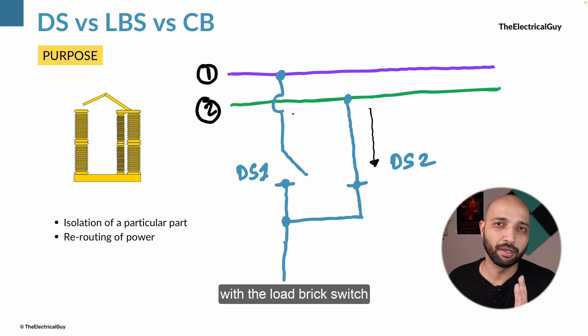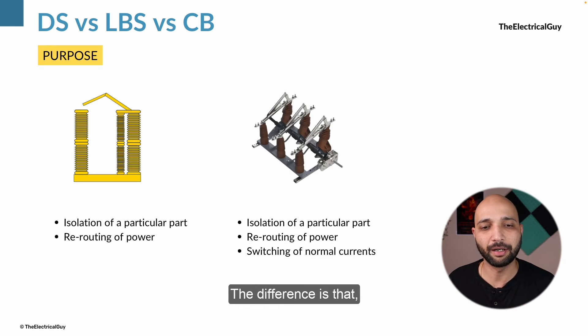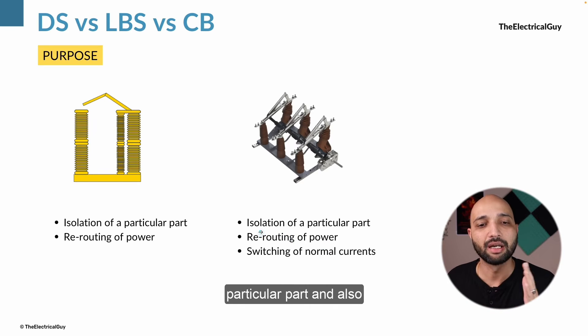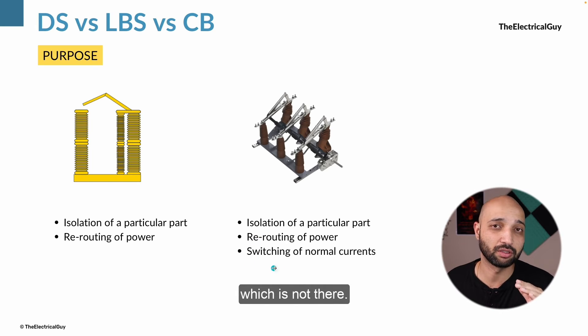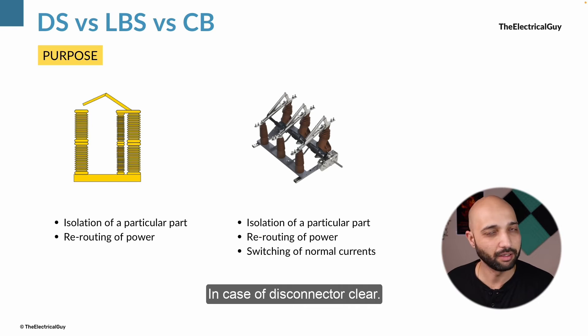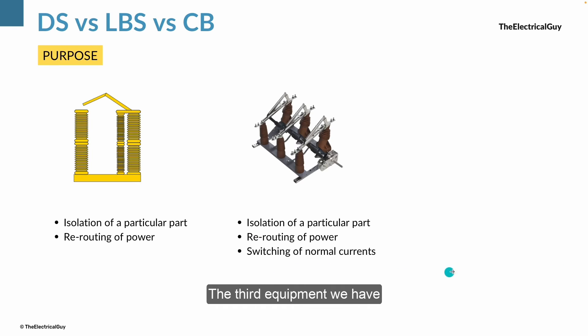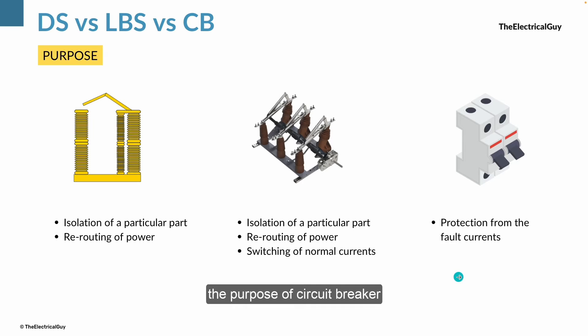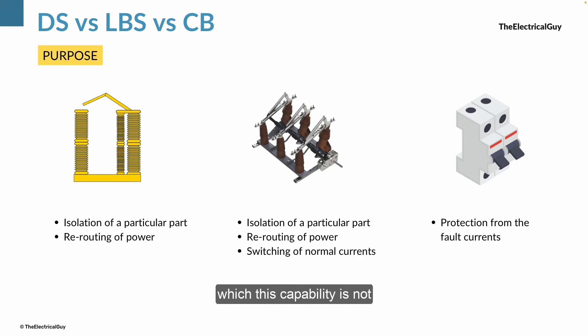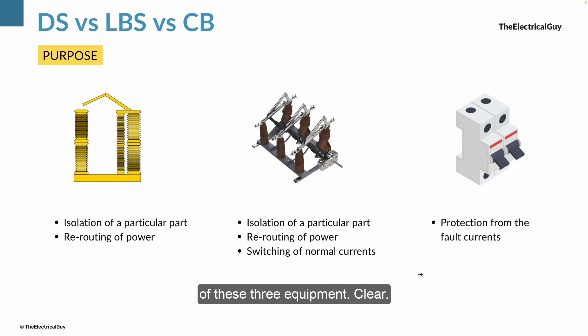Comparing with the load break switch or switch disconnector: they are also capable of isolating a particular part and rerouting power, but additionally they are capable of switching normal currents, which disconnectors cannot do. The circuit breaker's purpose is to protect the system or circuit from abnormal short circuit currents — a capability not present in switch disconnectors or disconnectors.